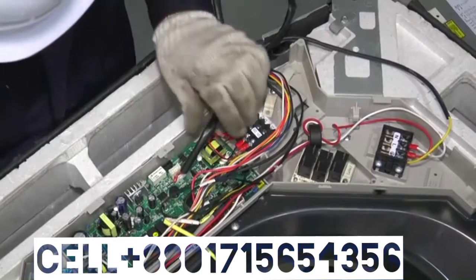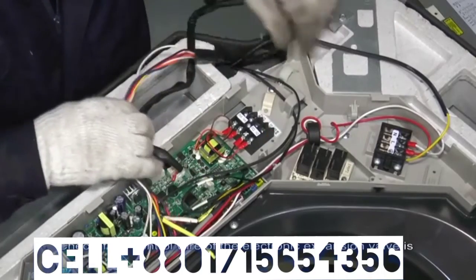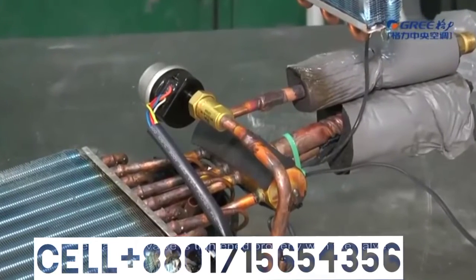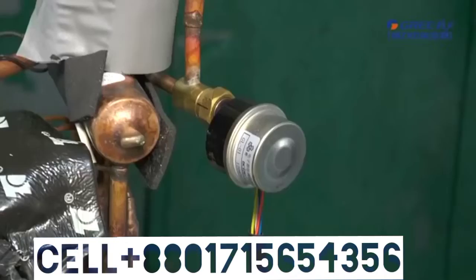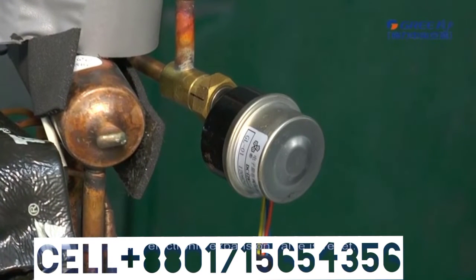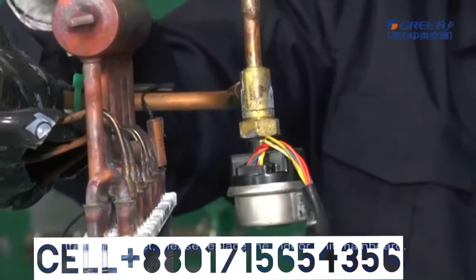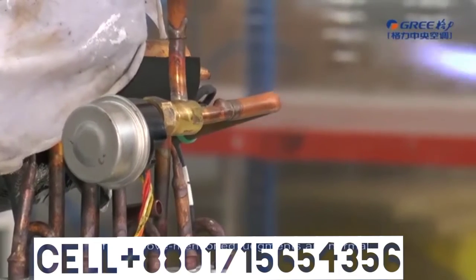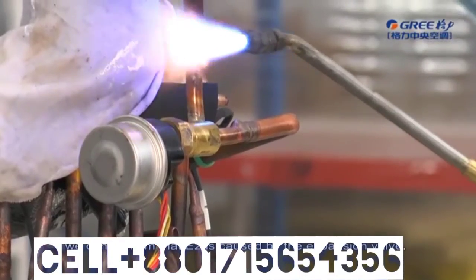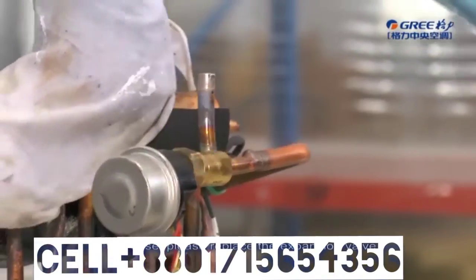In this case, please check the following items. Check if the control wire of the electronic expansion valve is connected well to the mainboard, and if the coil of the expansion valve is tightened properly with the valve. De-energize and then energize the expansion valve to see if the electronic expansion valve is reset. If it is not reset, please replace the indoor unit mainboard. If the above-mentioned judgments are normal, we can confirm that the E2 is caused by the expansion valve. In this case, please replace the expansion valve.